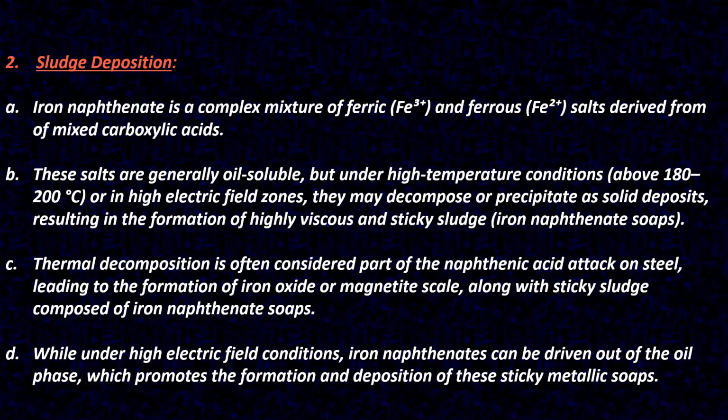These salts are generally oil soluble, but under high temperature conditions, that is above 180 to 200 degrees centigrade, or in high electric field zones, they may decompose or precipitate as solid deposits, resulting in the formation of highly viscous and sticky sludge from naphthenate soaps. That is iron naphthenate soaps, sticky sludge.